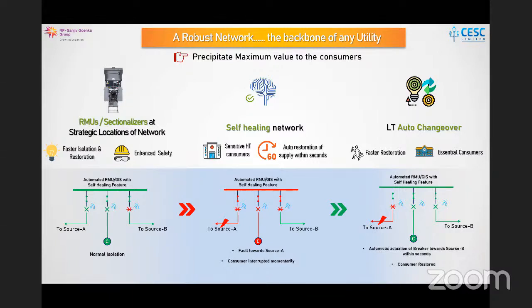If we have a remote operation kind of regime from the SCADA, then the self-healing network for very sensitive consumers, wherein within milliseconds, if one feed goes off, the other feed would automatically come into play without even intervention from the SCADA. Even changeover on the LT side, for very essential consumers like hospitals and nursing homes, we can think of LT changeover.